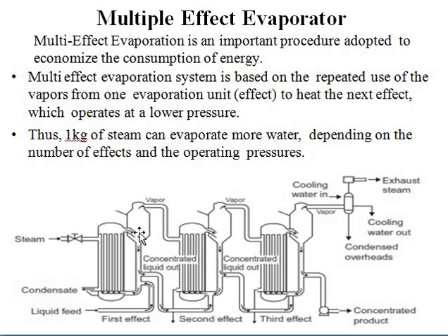It will come into this separator. The vapors will be separated and the concentrated food will be separated from this portion. Clear? These vapors have some energy. In the single effect evaporator we condense them, meaning we provide extra energy to condense them, but here these vapors have some energy and will go to the second section. Clear? So the temperature in the first section will be very high and it will be reduced in the next section, and after that it will reduce again in the next section.